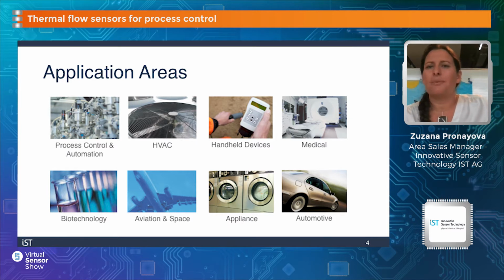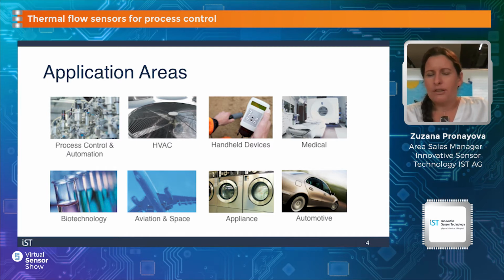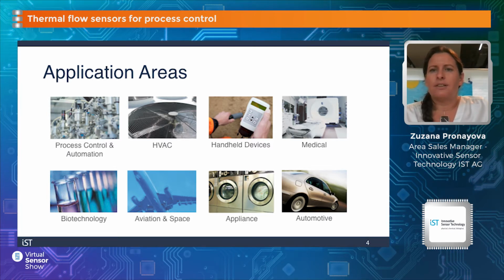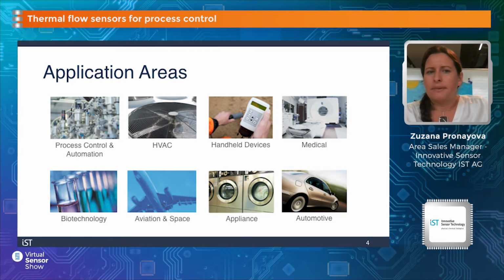As a small example, in aviation, a flow sensor is required to operate for many years, while the same sensor element can also be integrated into a disposable medical device where the operational lifespan of the sensor is in hours, or maybe even minutes. But still, both of them, of course, require a low drift sensor.